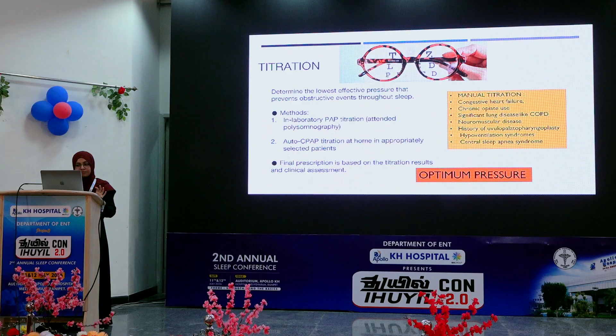What is the leak assessment? Because whatever pressure is set, it won't reach the therapeutic level if the leak is high. The allowable leak is about 24 liters per minute, which is the unintentional leak that happens through the exhalation ports. And we have to look at the residual AHI at this particular pressure. You can see that it is 6. We allow a little leeway of up to 10. And then we look at the frequency.